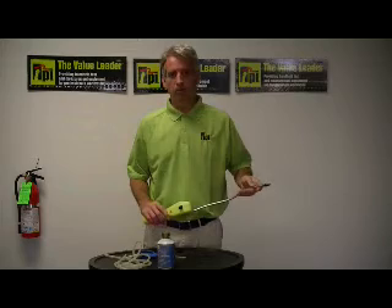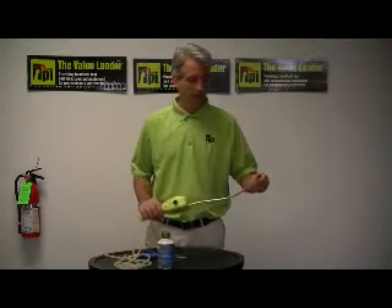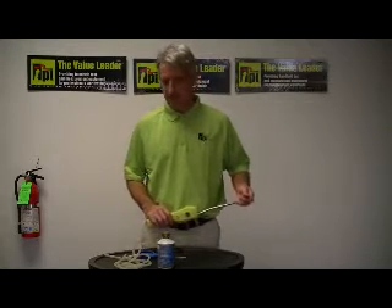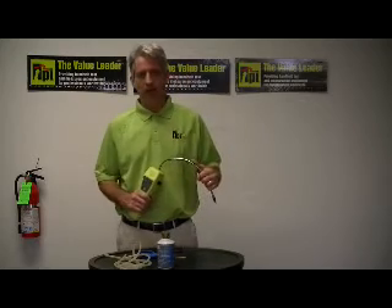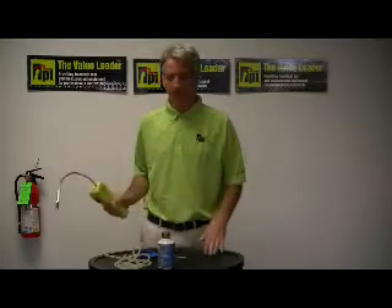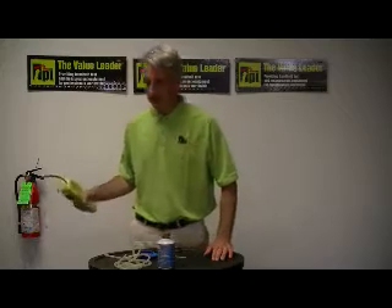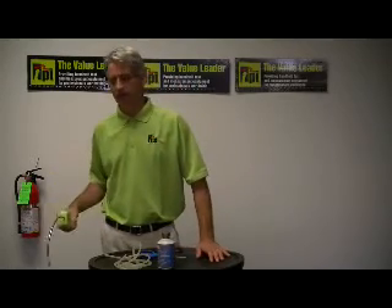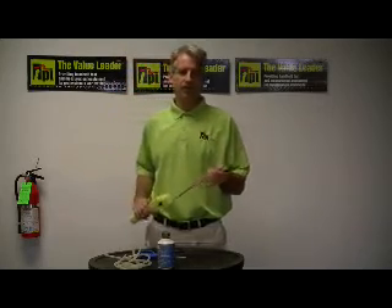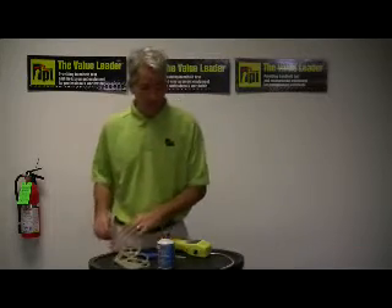One of the things I hear most often from technicians across the country is how can I make sure my leak detector doesn't go bad? One of the main problems with leak detectors — the biggest maintenance issue — is that these tips can often be exposed to oil, gas, and muck. If you're running across a dirty environment and exposing the tip to those things, it can be very sensitive and throw off the accuracy of your unit.